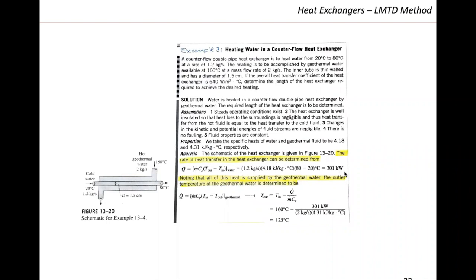Now that we know the heat supplied by the geothermal water, we can get the outlet temperature for the geothermal water. We apply the energy balance to the geothermal current — what we don't know is T_out. We plug in the heat transfer rate from the other current, because whatever the hot current loses, the cold stream gains. We get the outlet temperature for the geothermal water being 125°C.